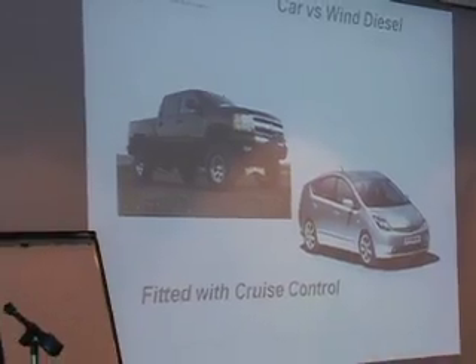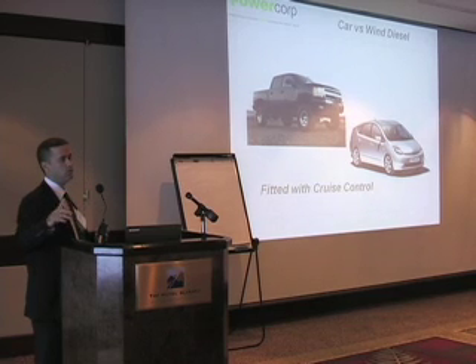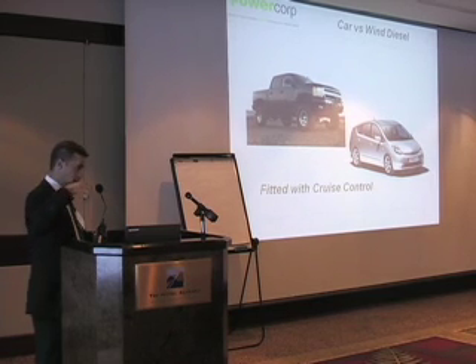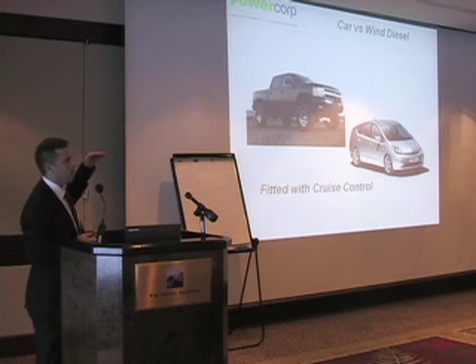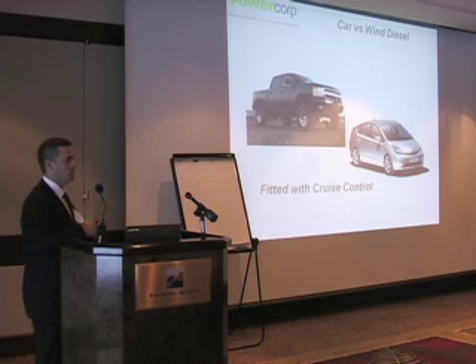For small hills, which most cars these days probably come factory fitted to handle with cruise control, the car can quite capably make its way up and maintain the speed set point you dialed in. The analogy is that the system frequency would be fine, the governors would just be given more throttle, more fuel would come in, and you make it up the hill. Likewise, going down the back side of that gentle hill, the governors back off, the speed setting is maintained, and the police don't pull you over for speeding.